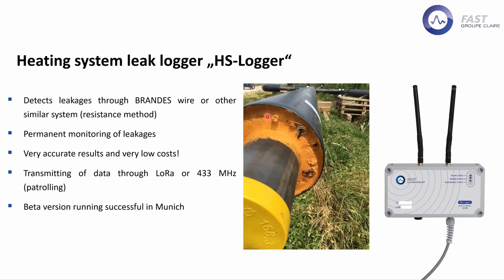If there is water leaking into the insulation, it reduces the resistance between the wires and also on the wire itself. And therefore you get a different value, which is then shown on the tablet. It's again similar to our noise loggers, but it's not the noise, it's the resistance you're measuring. You get a visual display of red, yellow, green. Green means everything is fine, the measurement didn't detect any leakage. Yellow, possible. Red, further investigate, of course.